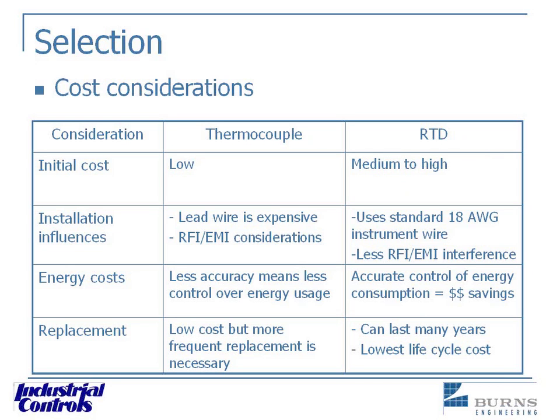Yeah, it's really about the total life cycle cost of that temperature measurement point. And most of the time, the RTD is going to be the best choice. And again, you need to start out by looking at that temperature range first. And if an RTD fits in your temperature range, that's really the one you need to look at. My experience out in the field has been, if you want accuracy, and you want that accuracy to last for a period of time, I would agree with you. The only time, again, I would go with a thermocouple is when it's beyond the temperature range of the RTD.